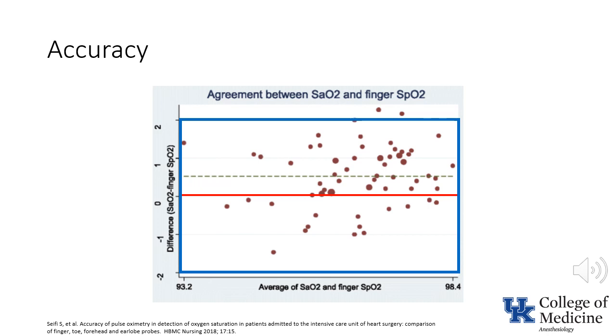In addition, the pulse oximeter was fairly precise. The blue box shows the bounds of plus or minus 2% compared to the values measured on the arterial blood gas. It's evident that values reported by the pulse oximeter were almost all within 2% of the value determined from the ABG. It must be kept in mind, however, that all of these values range between 93 and 98%.